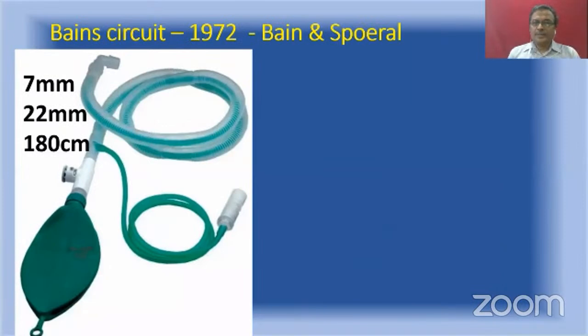Now, when you consider the Bain circuit, I said it was introduced by Bain and Spoerel in 1972. Let us consider its anatomy. There is an inner tube. You can see there is an outer tube. The inner tube has a diameter of 7 millimeters. The outer tube has a diameter of 22 millimeters, and the length of the circuit comes to about 180 centimeters. You can see the inner tube is extended out, and this is connected to the machine. There is an APL valve, which is not heavy, and there is a reservoir bag also.